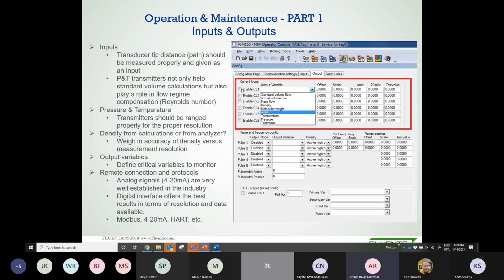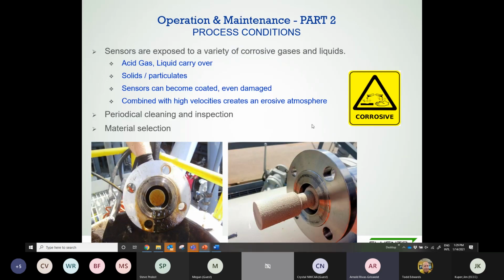Like I said, many of the manufacturers out there will have different options, either analog or digital, but what gives you the best value? That's what it is. In many circumstances, I would recommend Modbus, because you're not limited to a certain number of outputs. You have the whole array of variables available in Modbus, and you can pull from these variables as you wish. Then you can have that information in your DCS, do calculations, and make sure you get the data you need. So, okay, that covers this part.